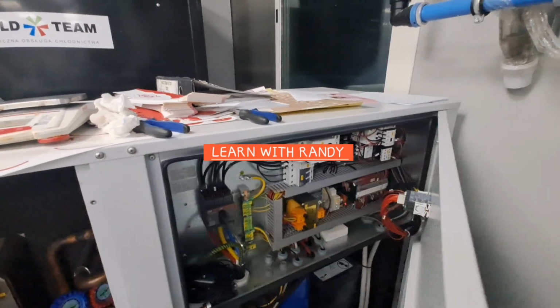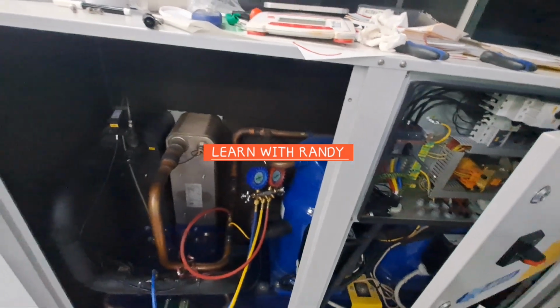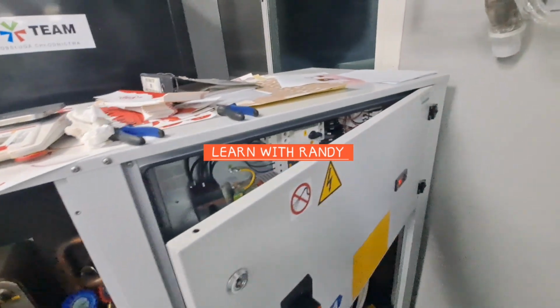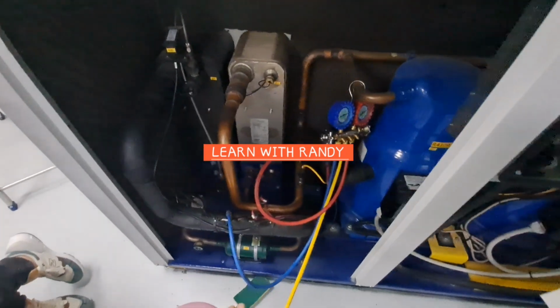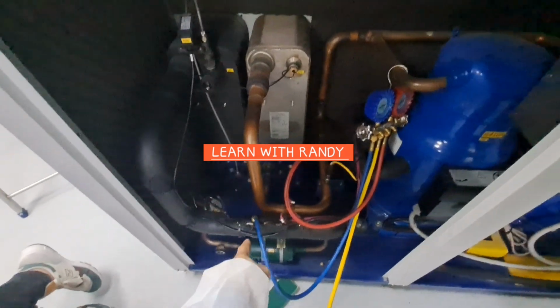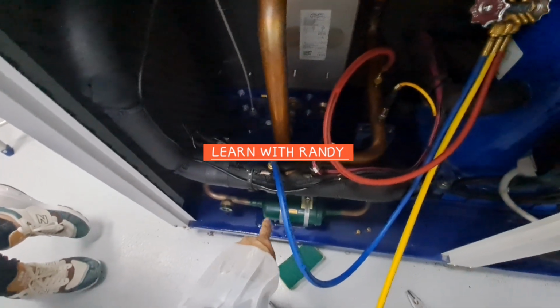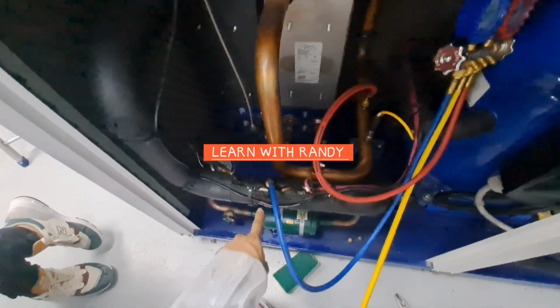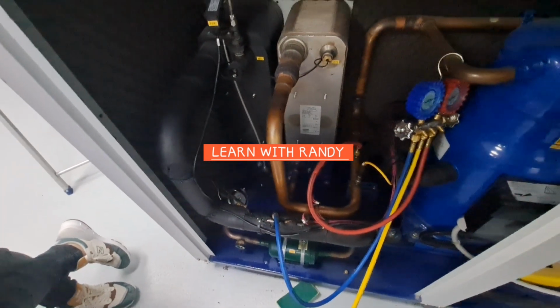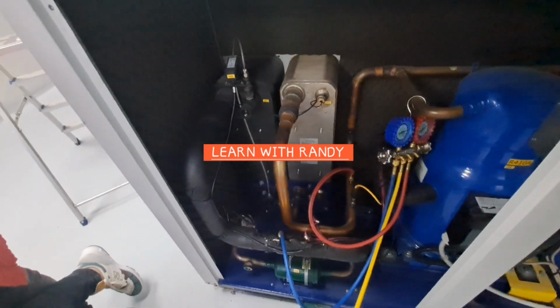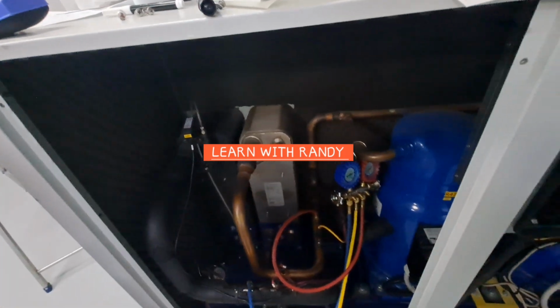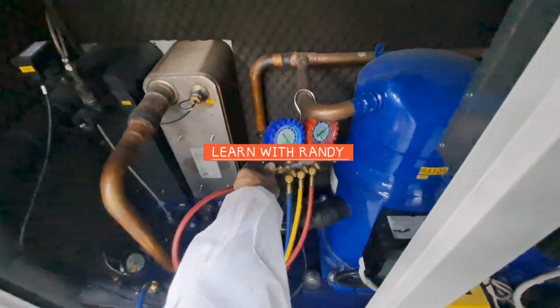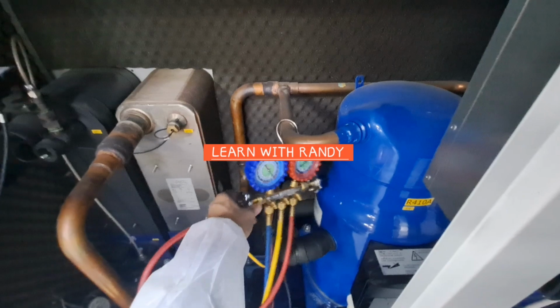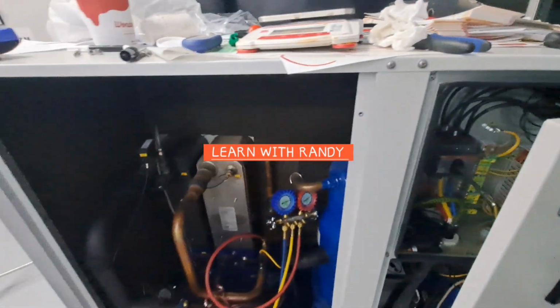That is the design. So I came here, I checked the system, and I found there was an error. I opened the unit and found that there is a gas leakage here. There is a problem with the suction valve. The suction valve is releasing gas. After some time, it released the gas to almost empty. Now I am charging it with this R410 gas. I got the right pressure, and then I restarted the unit.